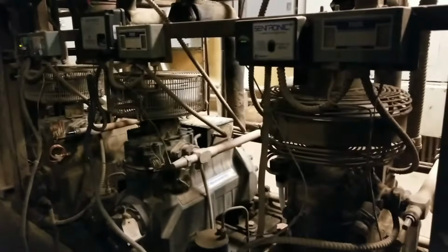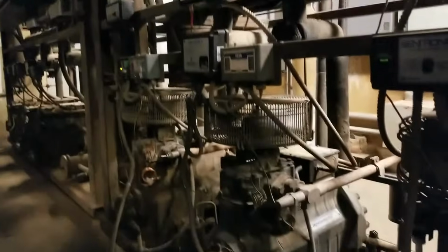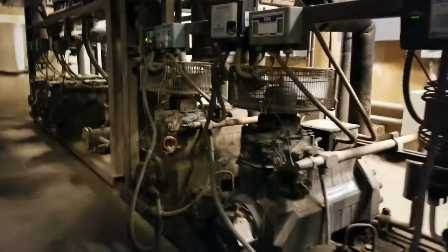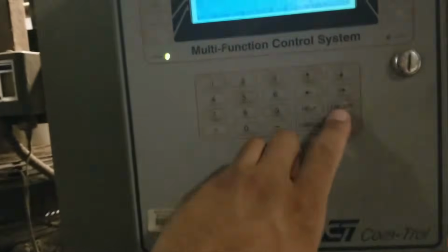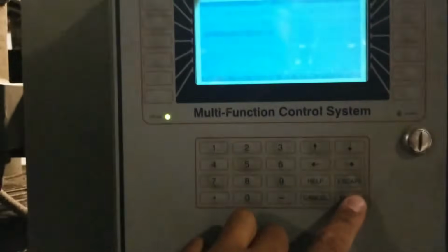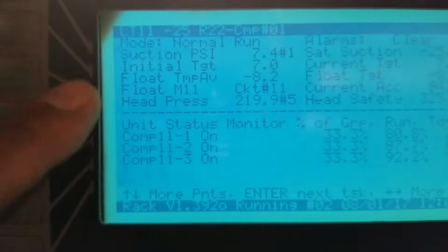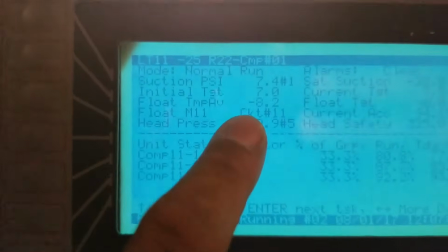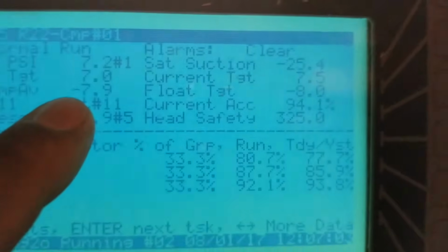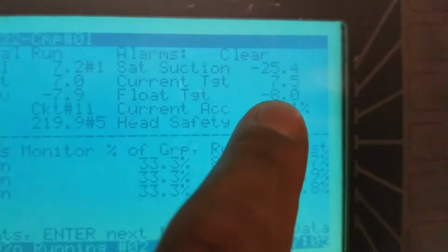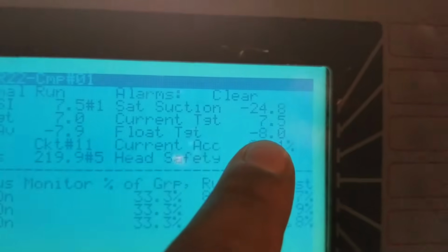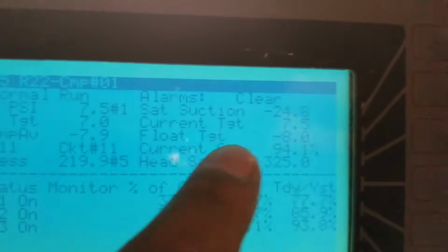Alright guys, after I fixed the compressor over there that had the high pressure and got my suction back online, all my compressors are running, but I did notice that the cases did not drop down like they should. And this is off of a floating circuit. So you see where it says float temp? The set point for the float target is -8. That's where we want the temperature to float. That's our target set point.